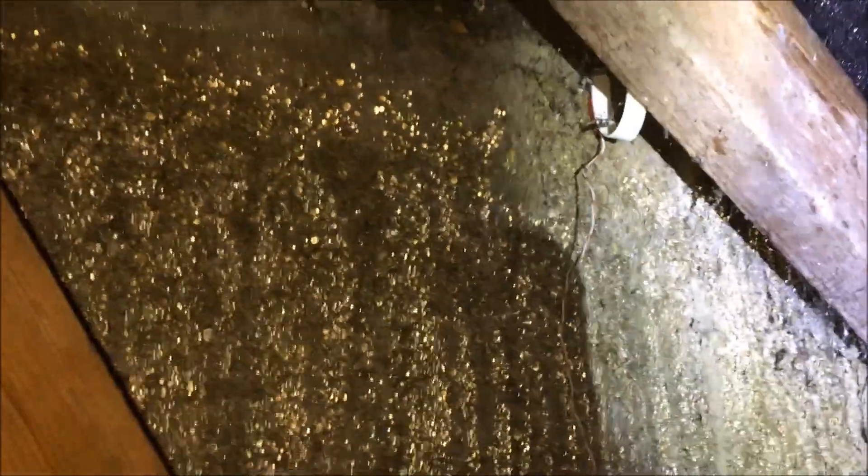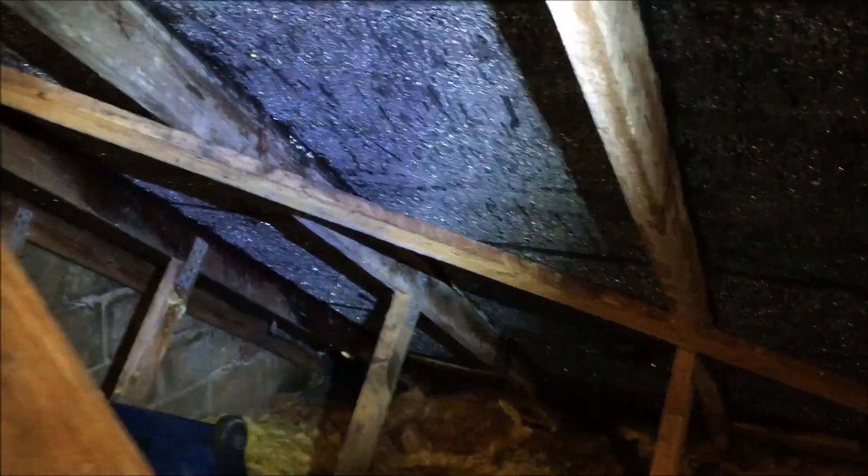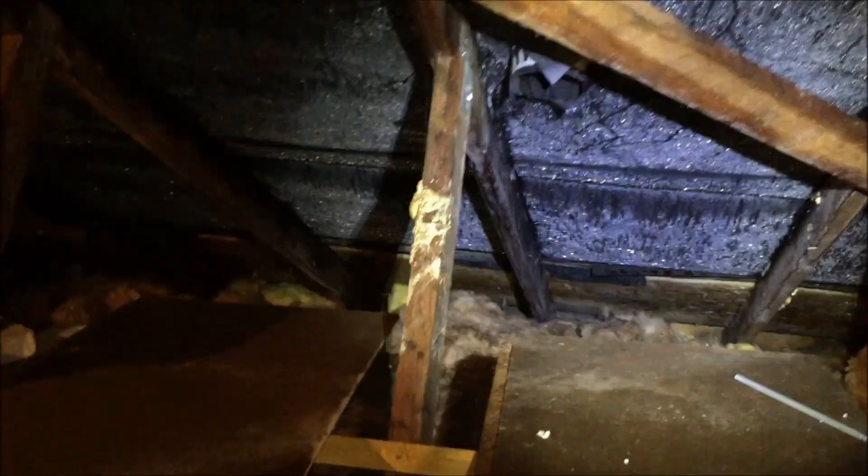We've got a surface temperature measurement there, measuring the temperature on the gable. We've also got one measuring the roof — that's measuring the temperature rate and the vapor pressure. What we're going to do is see exactly how the moisture is moving through the building. We've also got sensors inside to measure the ventilation and see exactly what's going on. We'll check all the roof ventilation, then we can put a fix together. Thanks for watching.